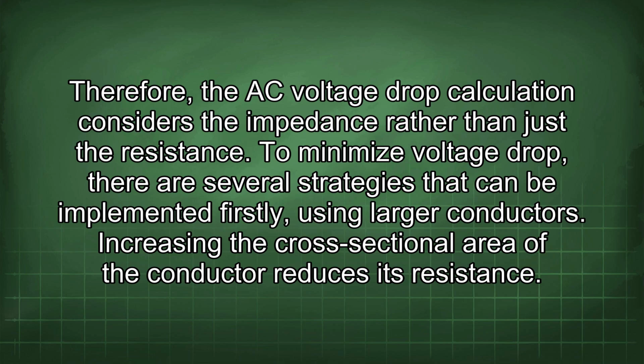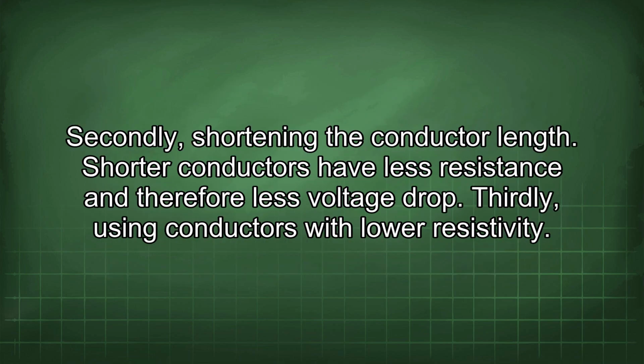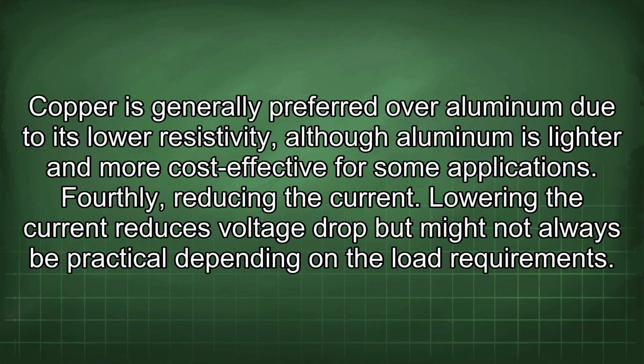To minimize voltage drop, there are several strategies that can be implemented. Firstly, using larger conductors. Increasing the cross-sectional area of the conductor reduces its resistance. Secondly, shortening the conductor length. Shorter conductors have less resistance and therefore less voltage drop. Thirdly, using conductors with lower resistivity. Copper is generally preferred over aluminum due to its lower resistivity, although aluminum is lighter and more cost-effective for some applications.